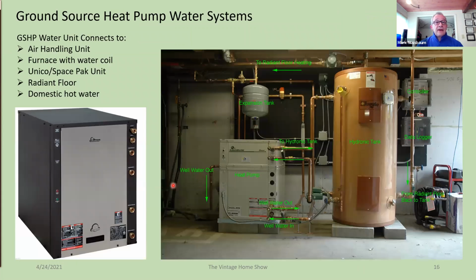And then the water system, again, this box is connected to the ground loop, and it produces chilled water at 40 to 45 degrees, and it produces hot water up to 120 degrees. And then you can circulate that through piping to water coils that are mounted in air handling units, furnaces, Unico, Spacepak. You can use heating only applications for radiant floor. Again, you can make domestic hot water directly out of this machine or through an indirect water heater if you wanted a larger volume. And so they're very flexible. Of the geo choices, this is probably one of the more expensive ones, and it's also one of the least efficient ones.